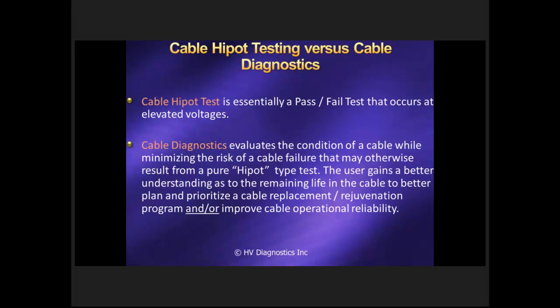So, just in summary, for the monitored withstand test we are still going to be using an AC tester, make no mistake, but if you just treat it as a pure withstand test, it's a pass-fail type test. Where you're looking at diagnostics, we're getting a better understanding as to the condition of the cable. And that's quite useful. You can start to do proactive cable replacement, or sections of the cable can be replaced based on what you see with the diagnostic.